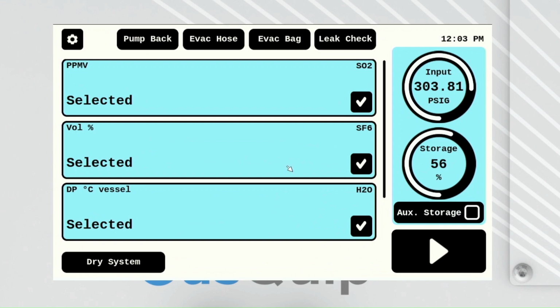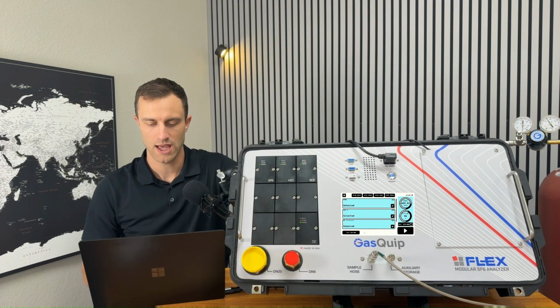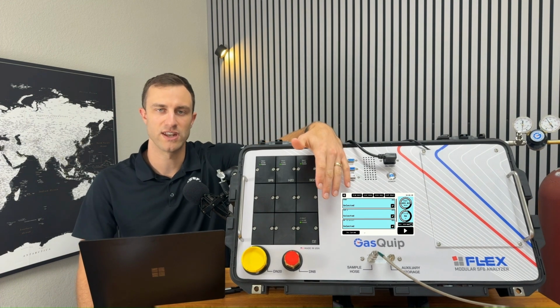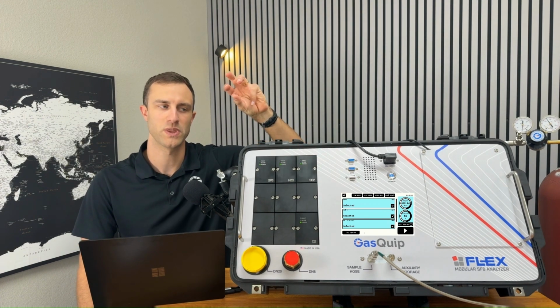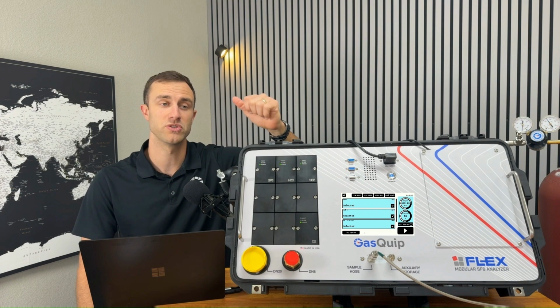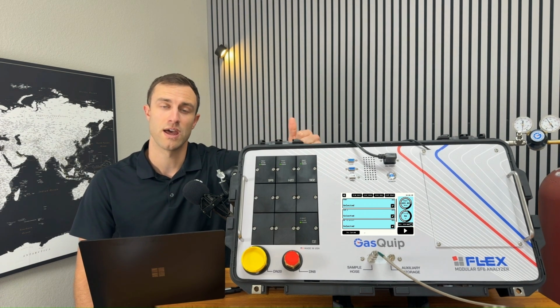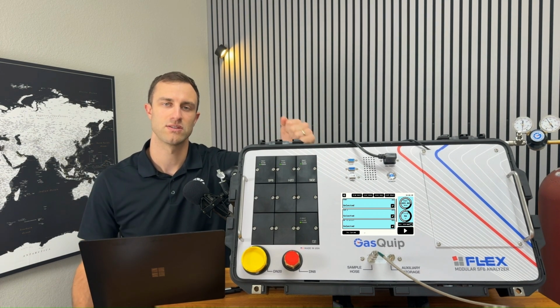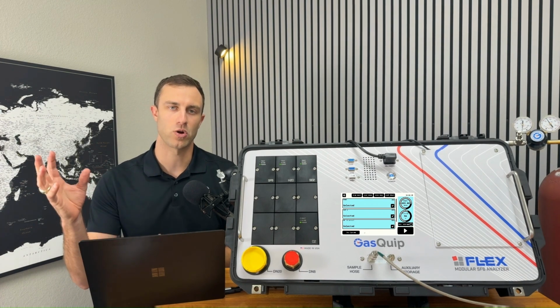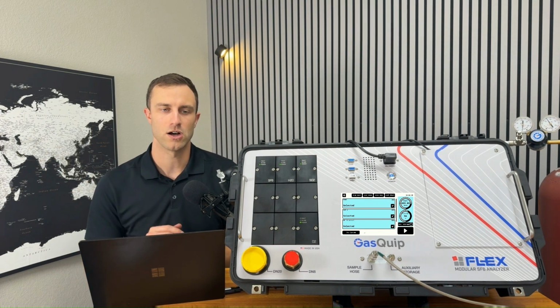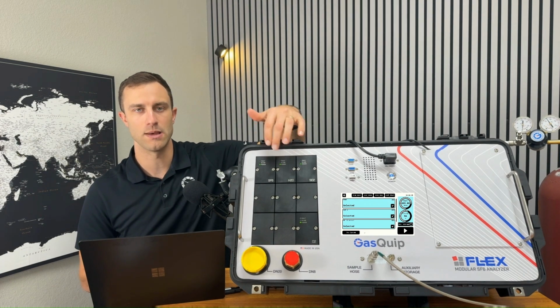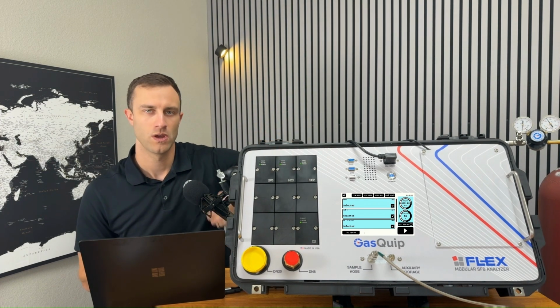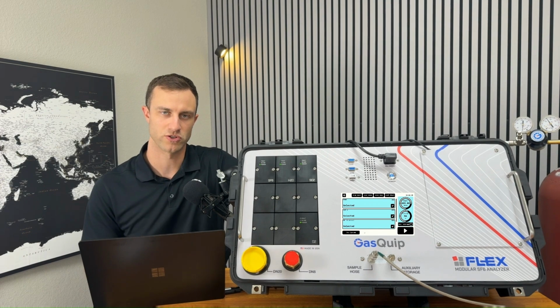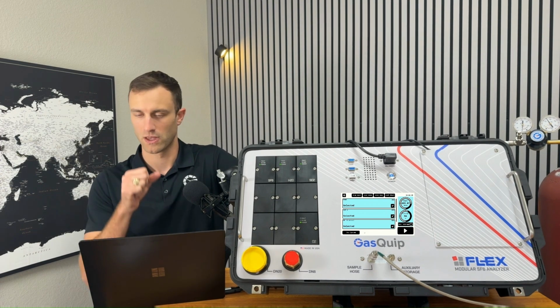Down here we have a dry system function. What this does is pull an evacuation on all of our modules and also our inlet fittings and connections. So all the internal plumbing plus the module manifold, it pulls an evacuation on those and holds it and runs that for about 5 minutes. That way it can help burn off some of that residual moisture, and also runs the heated tip on the H2O sensor, which helps burn off some of the residual moisture that might be found in your system.